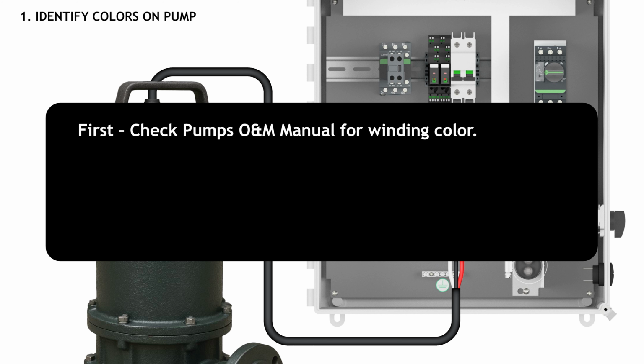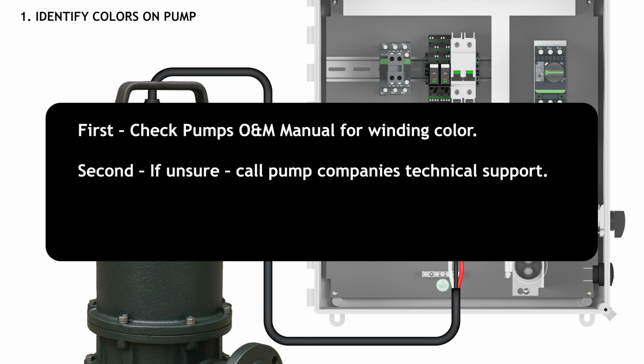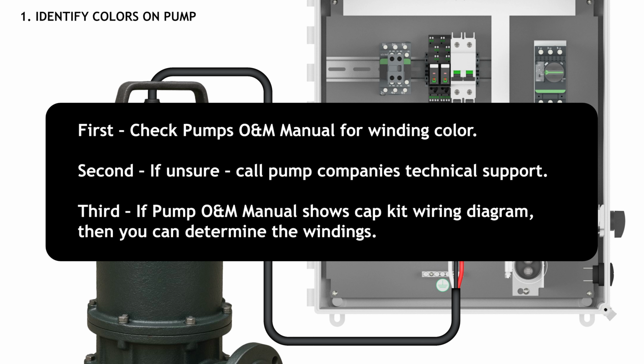First, check the pump's owner's manual, and if they specifically call out the winding color with the associated winding, then you can proceed to connect these wires to the control panel. Second, if the owner's manual is unclear, then call the pump manufacturer's technical support group and ask specifically which pump winding color is associated with the common, main, and start windings. Third, if the pump manufacturer's owner's manual shows a wiring capacitor kit diagram and shows pump wire colors connected in the wiring diagram, then you can determine the windings.